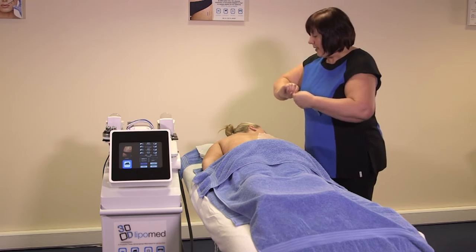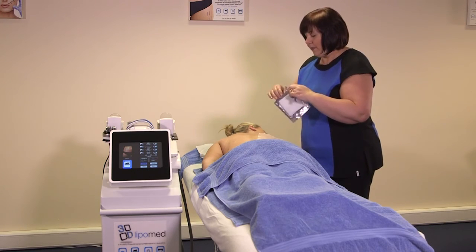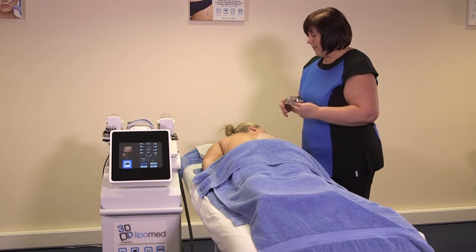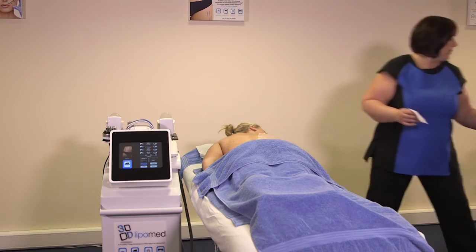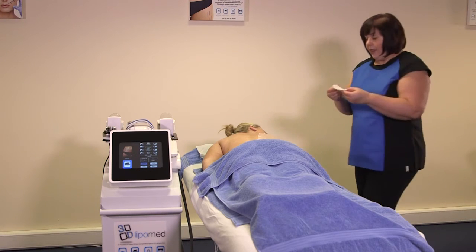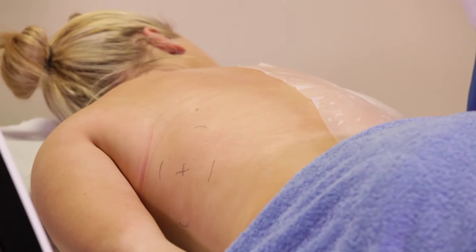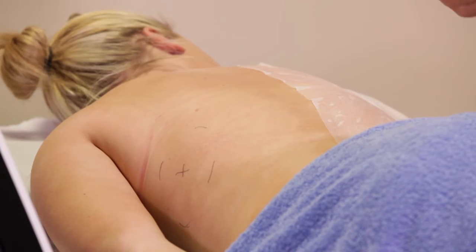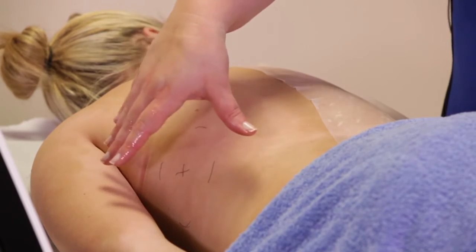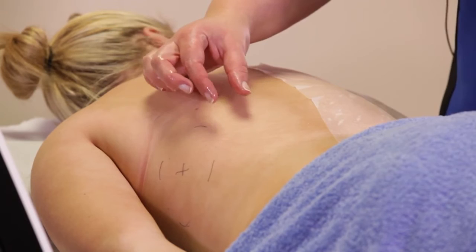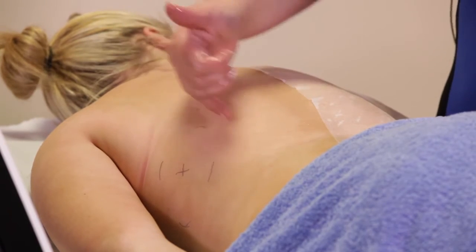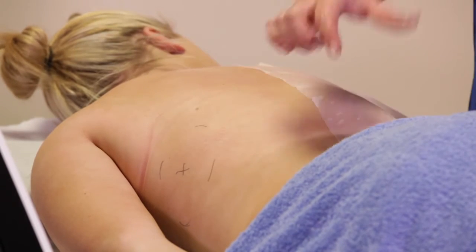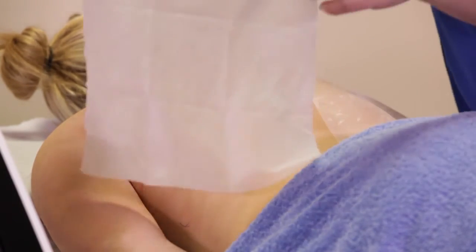Your second pad then needs to go onto the skin in exactly the same manner, but also ensure when you're doing a Cryo Duo that each head is at least 3 centimetres apart from the other, because the vacuum obviously pulls the skin into the head. If the heads are too close together, then there'll be too much stretch on the skin in the middle. So you need to make sure you've got at least 3 centimetres. We've got plenty of room here, but just be careful when you're applying on the abdomen.